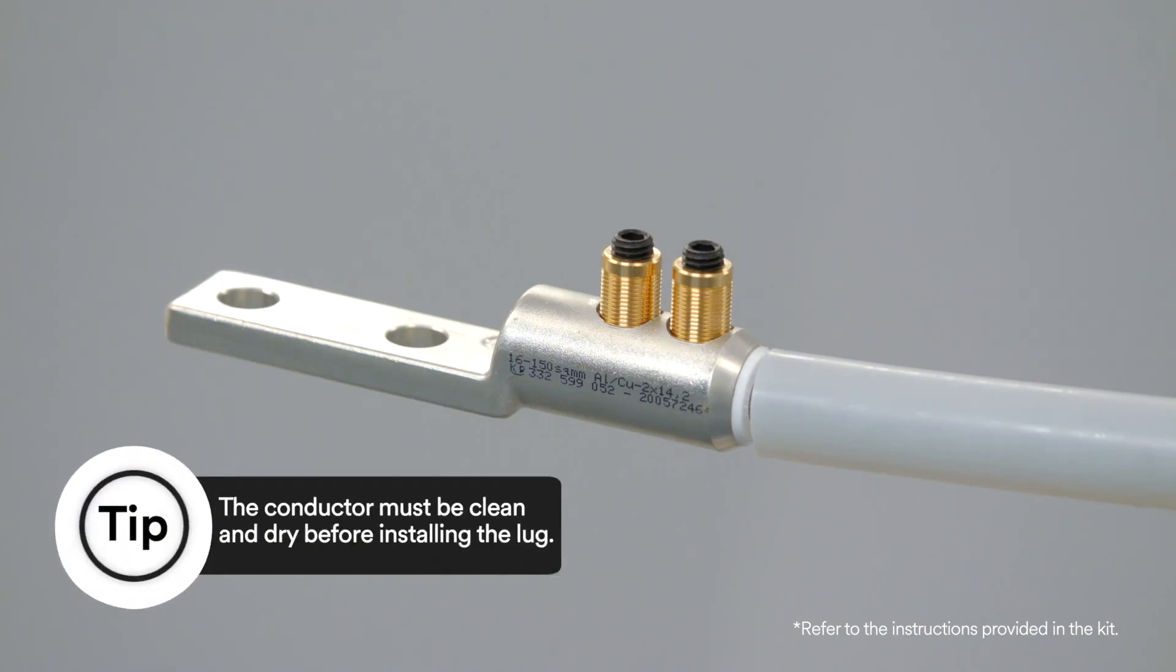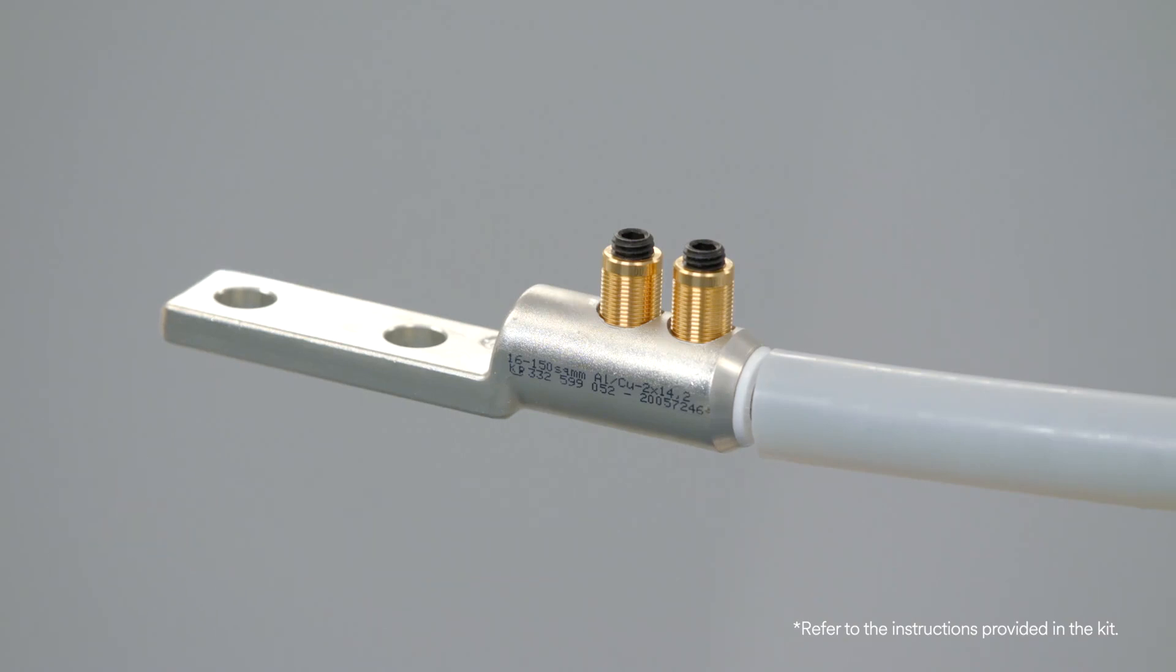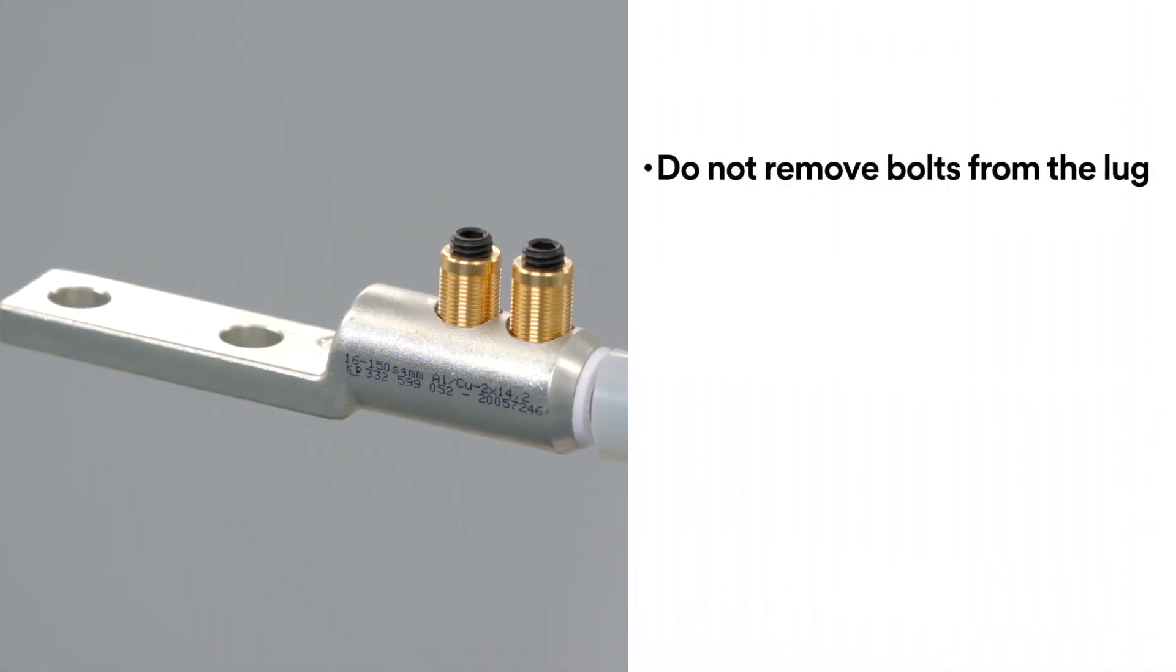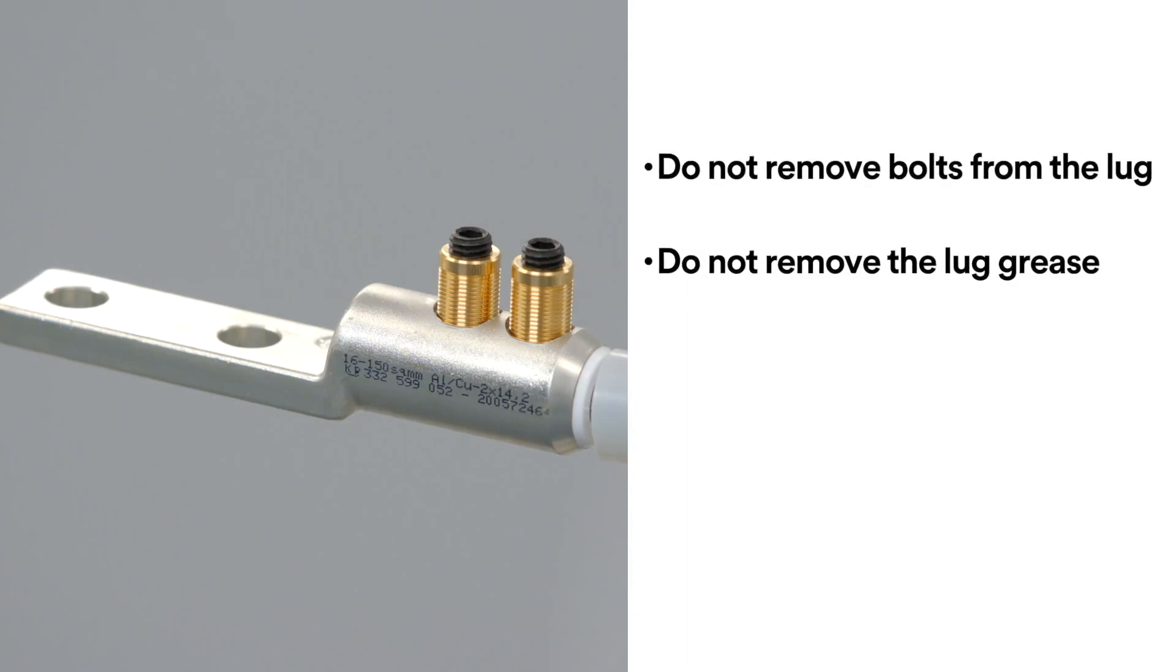For this video we will be using the 3M Mechanical Shear Bolt two-hole lug QL2 series. When installing the lug there are a few things you must remember. First do not remove bolts from the lug and do not remove the lug grease as it is pre-greased for the installation.